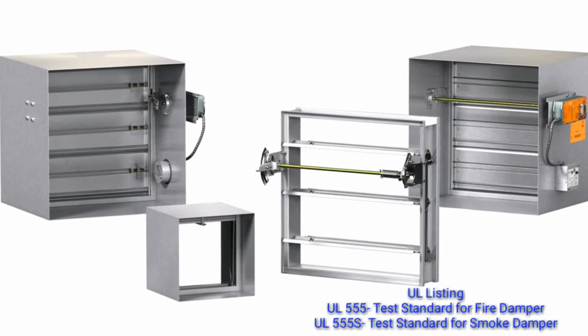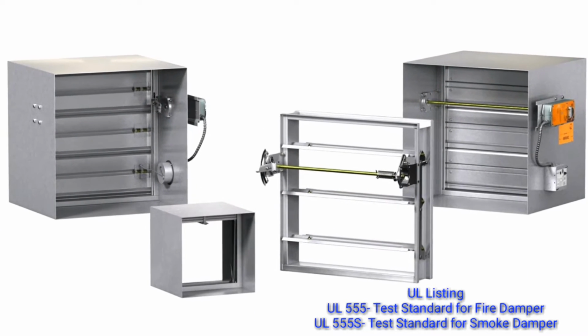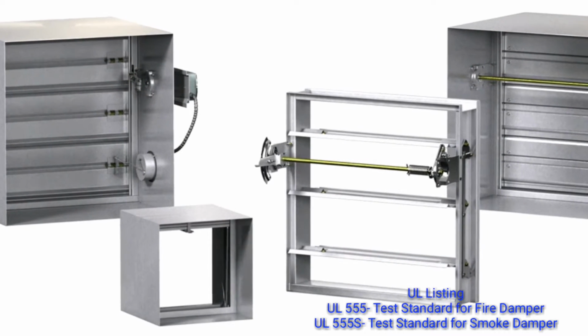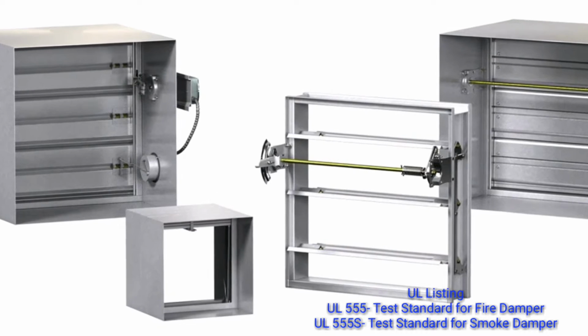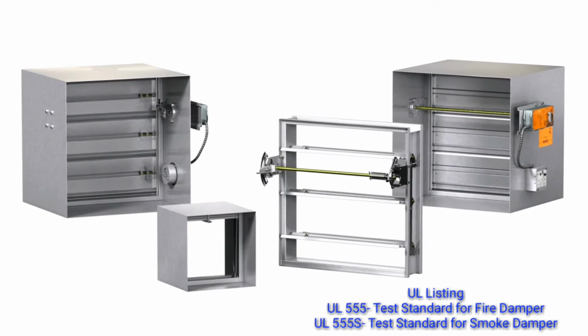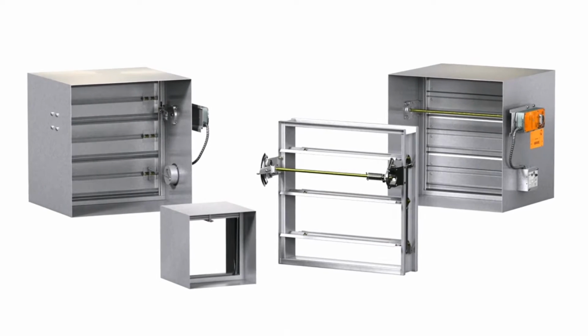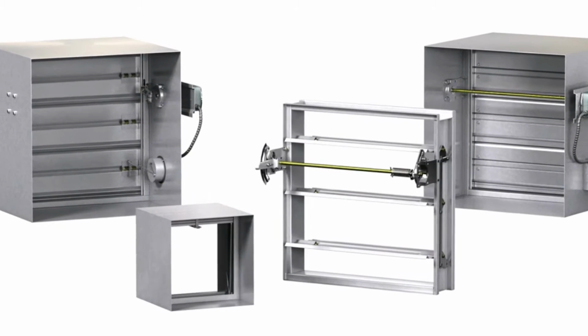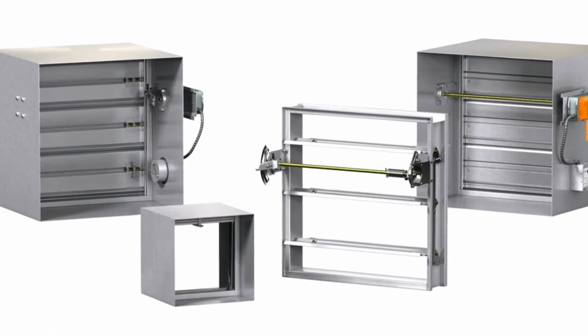All dampers must have UL rating. UL refers to Underwriters Laboratory. UL 555 is the test standard for fire damper. UL 555S is the test standard for the smoke damper. Combination of fire and smoke damper must meet the test requirement of both UL test standards, that is UL 555 and UL 555S. Based on this test, dampers are given a fire rating and leakage rating.